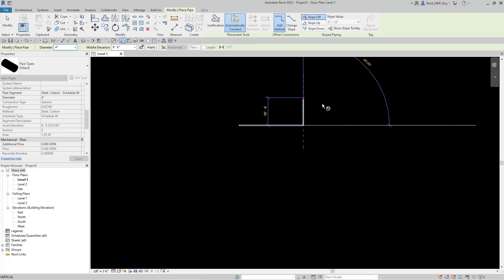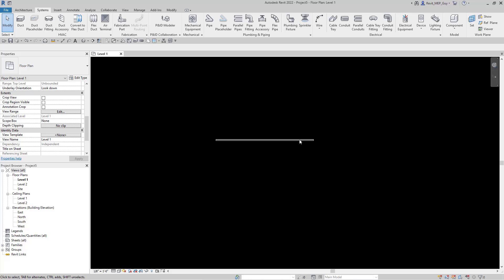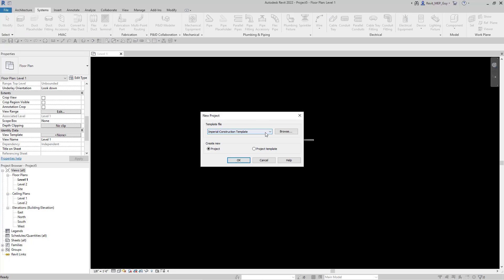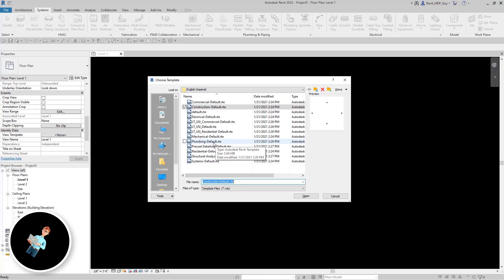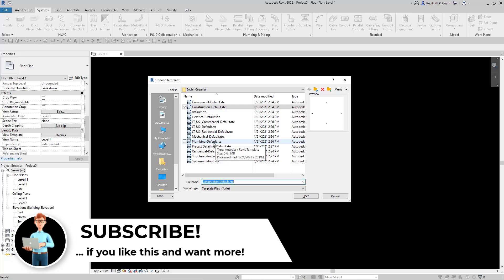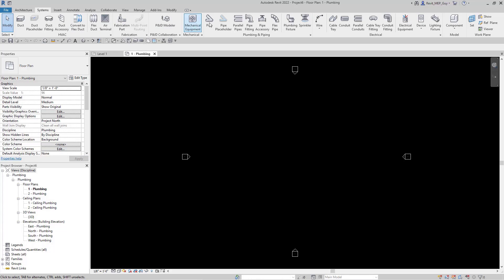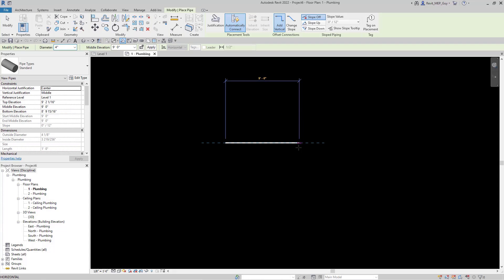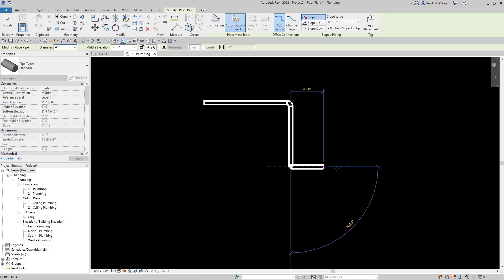Again, remember when we try to draw pieces of pipe at an angle or at a 90, it's not working because we don't have our fittings. The best way to load in your fittings is to actually open up a Plumbing template. So I'll go back to File, go to New, hit Browse, and find the Plumbing Default template — it'll be in a certain location on your computer, you'll have to find it. We're going to use Plumbing Default, which is an RTE file. Hit Open, hit OK, and Revit has loaded this plumbing project. Now if we go to System Pipe, zoom in, make detail level Fine, and draw a 90 — as you can see, everything's working.